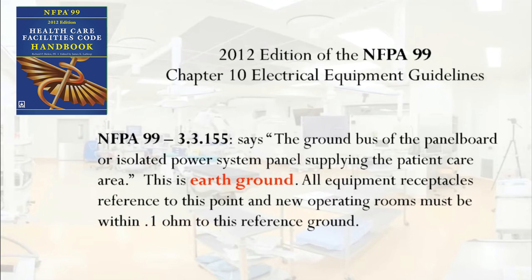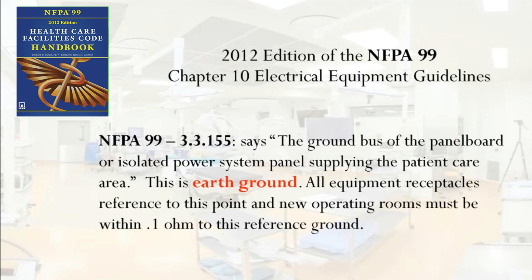NFPA 99 section 3.3.155 says the ground bus of the panel board or isolated power system panel supplying the patient care area — this is earth ground. All equipment receptacles reference to this point, and new operating rooms must be within 0.1 ohm to this reference ground. This means the panel board that has the isolation transformer in it is grounded to earth ground.